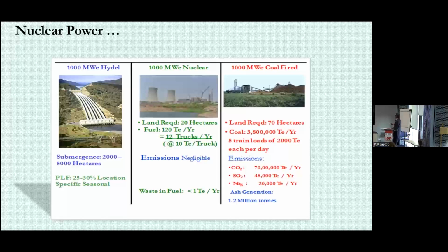Whereas for coal, for the same output, around 70 hectares of land is required, and the fuel required is coal - something like 38 lakh tons per year, which is 5 train loads of 2,000 tons each per day. We have many wagons moving, taking coal - a common feature seen everywhere. And you have emissions of 70 lakh tons per year of CO2 coming from this coal fire, plus ash generation of 1.2 million tons.